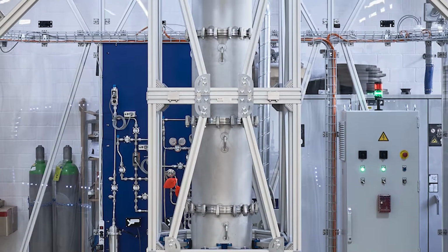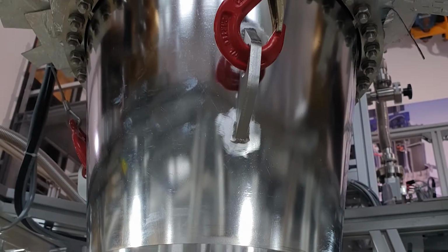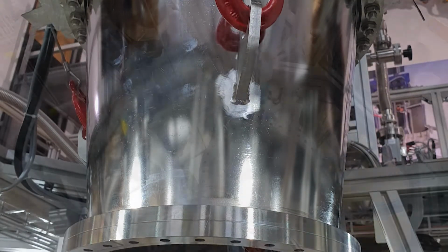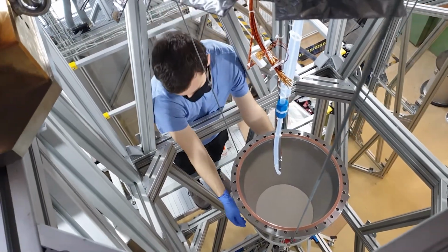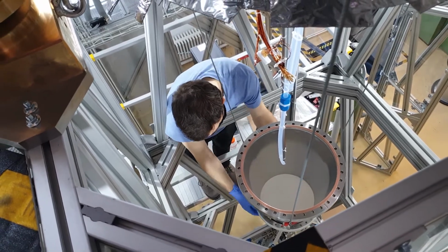This facility is not much different than the small-scale setups we have here, but is bigger and better. The heart of the system is the vacuum-insulated double-walled cryostat. The inner vessel is made of electropolished stainless steel to help the outgassing process, where trapped gases are released from the wall surface. It can contain up to 350 kilograms of xenon, operated at a temperature of around minus 100 degrees Celsius at a pressure of 2 bars absolute.